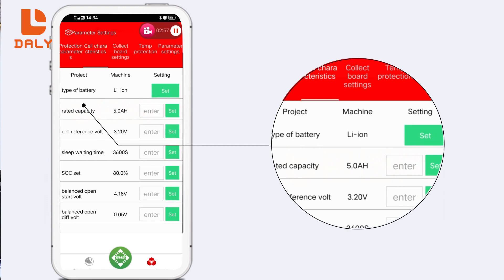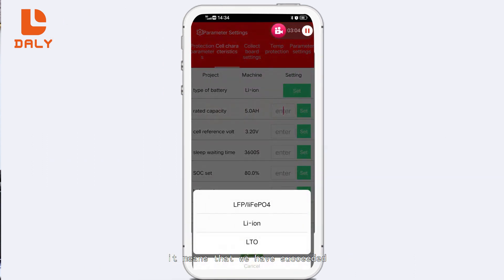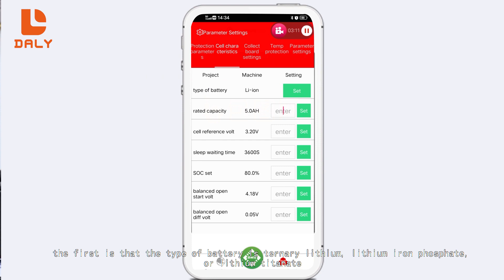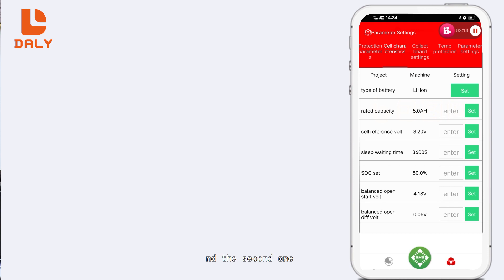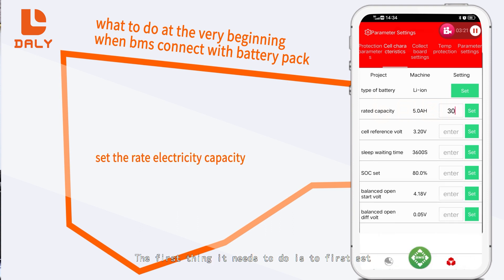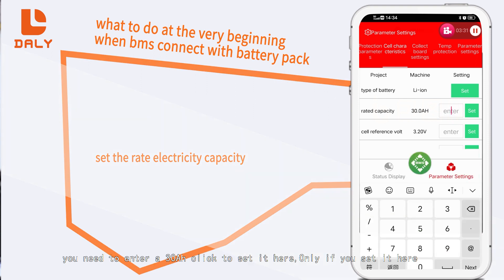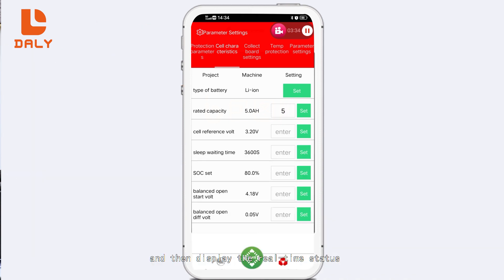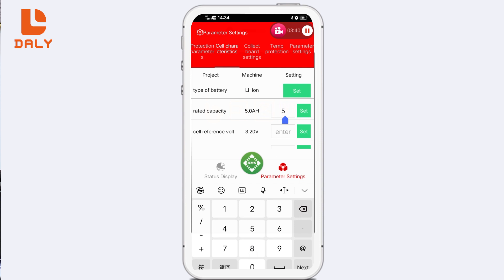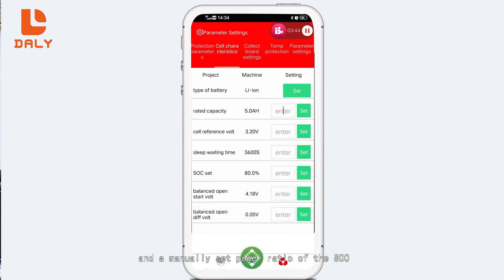Including over-discharge protection, we can also set it — for example to 2.8V — click settings, and when the machine parameter becomes 2.8V it means we have succeeded. Then we look at the second page. The second page features battery cell settings. The first is battery type: ternary lithium, lithium iron phosphate, or lithium titanate. The second is the rated capacity. The first thing to do when setting up the battery pack is to enter the capacity here — for example, if your battery pack is 30Ah, enter 30Ah and click set.